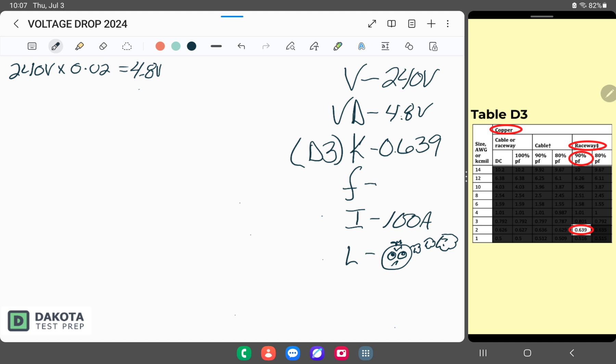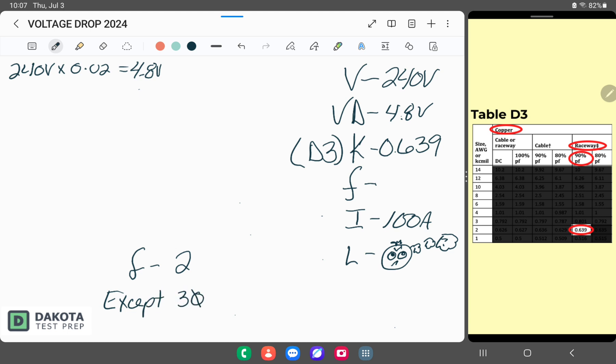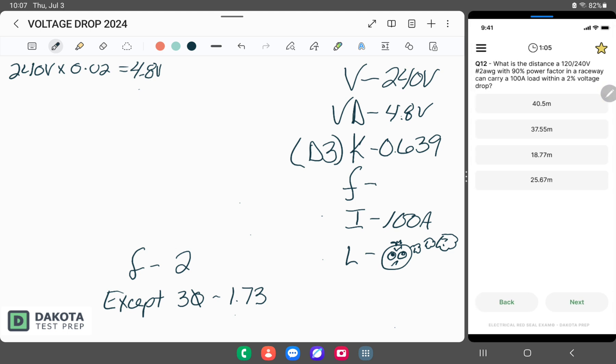The F factor is based off some fancy math. When it comes to the F factor, everything uses a multiplier of 2 — except if it's 3-phase. If it's 3-phase, we use our magic 3-phase number, which is 1.73. In the question we have, it doesn't mention anything about 3-phase, so we're going to use our multiplier of 2.